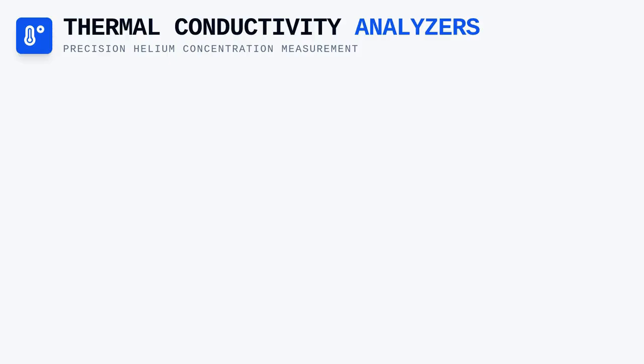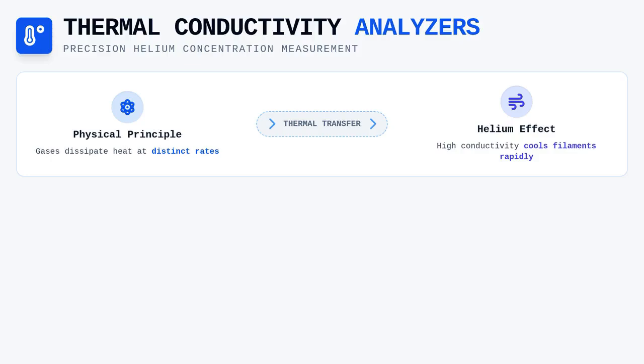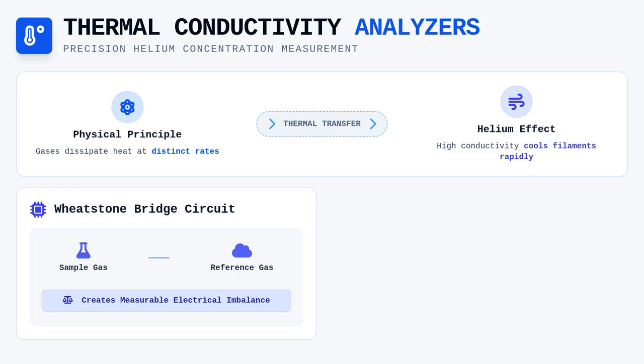Thermal conductivity analyzers provide a robust method for measuring helium concentrations, relying on the principle that different gases dissipate heat at distinct rates. These sensors usually consist of a Wheatstone bridge circuit, where heated filaments are exposed to the sample gas and a reference gas, such as room air. Since helium has a significantly higher thermal conductivity than nitrogen or oxygen, the presence of helium cools the filament more rapidly, creating a measurable imbalance in the electrical circuit.